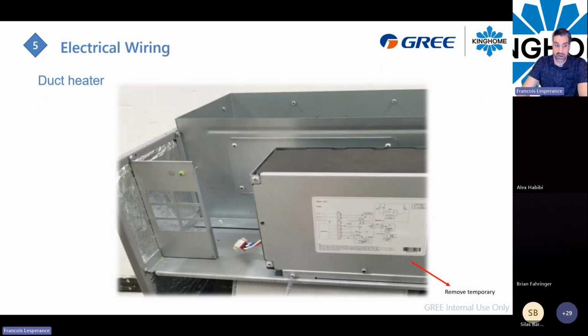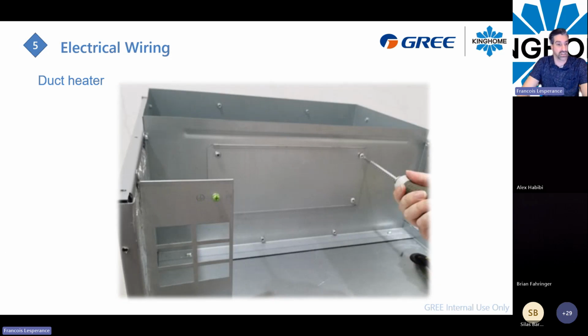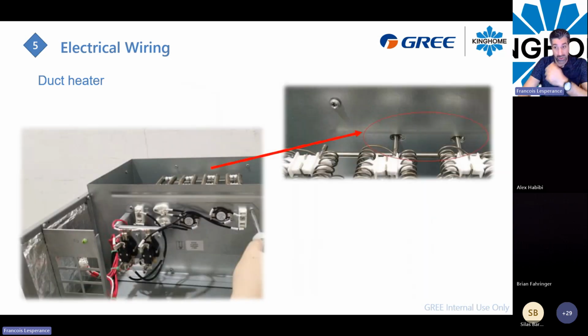If you install the duct heater, I have some slides here just to give you a small overview of what it looks like when you install an electric heater inside of that cabinet. But first thing first, you will have to remove the electrical box. So you have 2 screws just in front of the box, and you will have to remove it temporarily to give you enough room to install the duct heater. So you will just unscrew the metal plate in the back of the air handler, and you will install your duct heater inside of it.